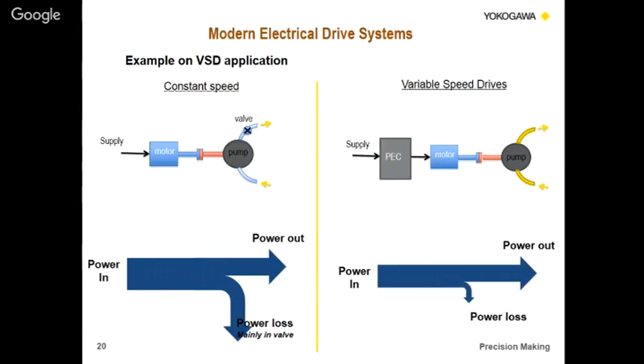Whereas here, we are putting in a variable speed drive, controlling through the drive depending on the load or pump requirement. The motor speed will vary so that the required amount of power is delivered to the end usage. This way, power losses will be minimized. With constant speed, the losses also remain constant, but with variable speed drives, we are minimizing the losses, reducing them further.